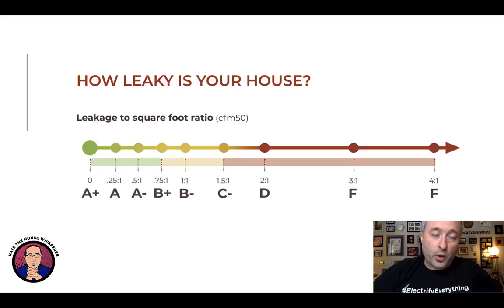Here's another quick way to look at that, just as review: it's the leakage to square footage ratio. So say you have a 2,000 square foot house with a 2,000 blower door number, or more correctly, the ratio would be a 2,000 blower door to 2,000 square feet. That's 1:1. If you have a 4,000 blower door to 2,000 square feet, that's a 2:1. So 1:1 is about when houses start to be controllable with HVAC alone. Is it guaranteed? No, it's not.